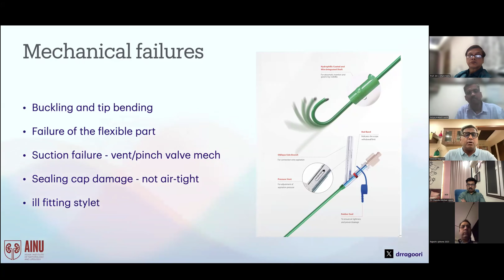A sealing cap damage, which is not airtight. The sealing cap is the one at the far end of the access sheath, where we remove the stylet, put back the sealing cap, and then introduce the scope, which keeps the suction intact. Now, if you don't use this, the water leaks continuously backwards. That doesn't give you an adequate suction effect. I would say that is more of a limitation rather than a complication.